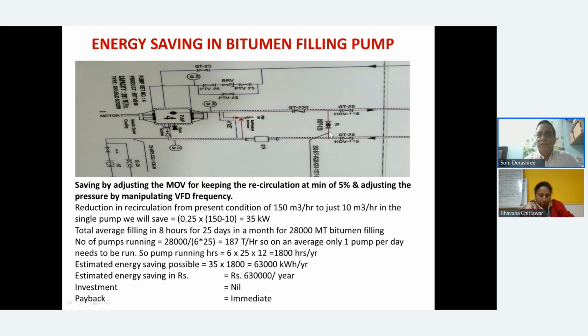quantity here. And this was actually just a safety margin of 5% because they had a bypass. I said it is also not required, but they had it in case my VFD fails. I said if the VFD fails, then even the motor will not run. But they said no, we want to have some safety, so we allowed them. Of course, there was a safety valve also, but this is a simple solution. Put a VFD here and run it. Earlier there was no energy saving, but here there is tremendous energy saving. Of course, it is not in proportion to the affinity law; here it will be just proportional to the flow.